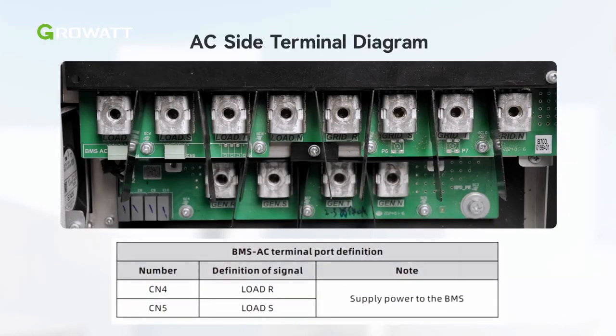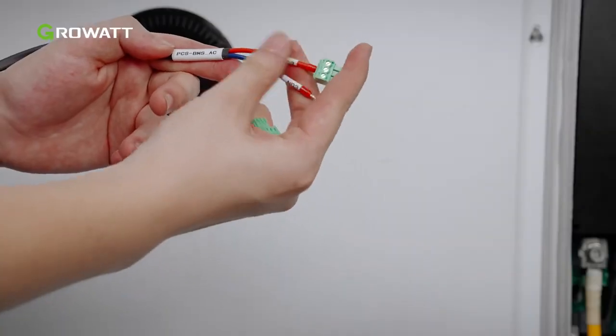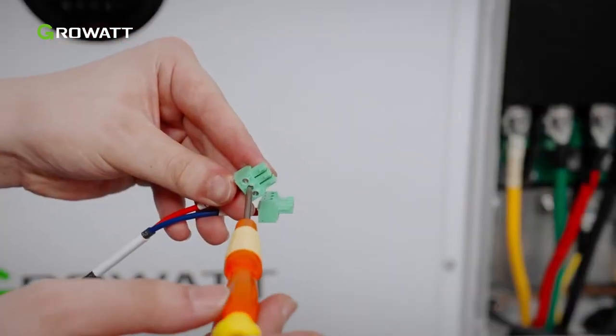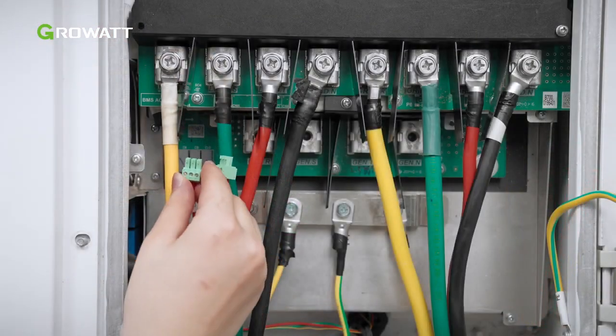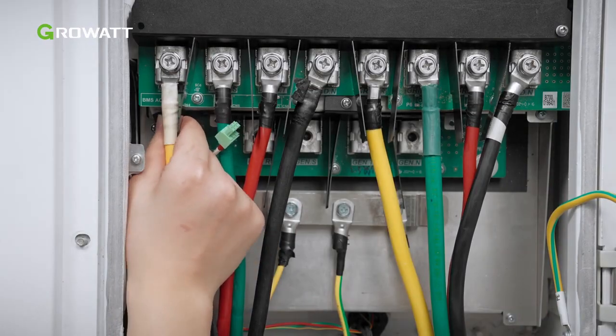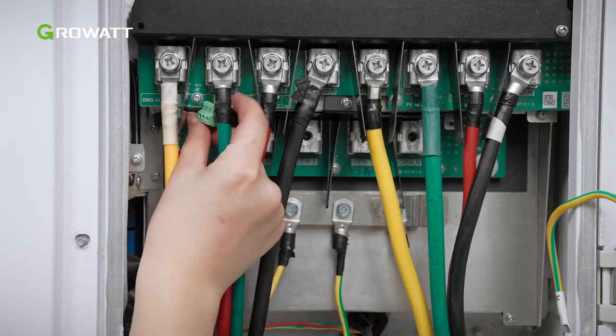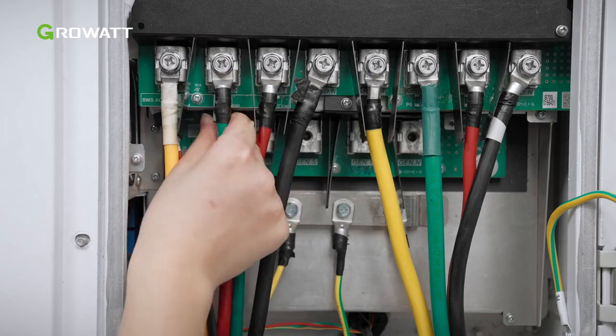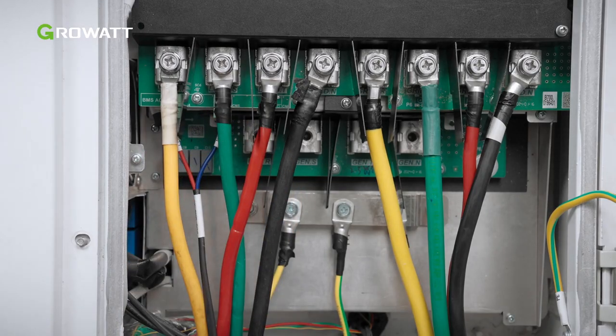The BMS AC terminal provides AC power to your battery system. Please connect the cable as required. Check the position of the BMS AC terminal before wiring. Assemble the BMS AC terminal and cable as shown. Then connect the BMS AC cable to the terminal. We recommend that you perform this step before connecting the other AC cables in case of a tight AC terminal entrance.